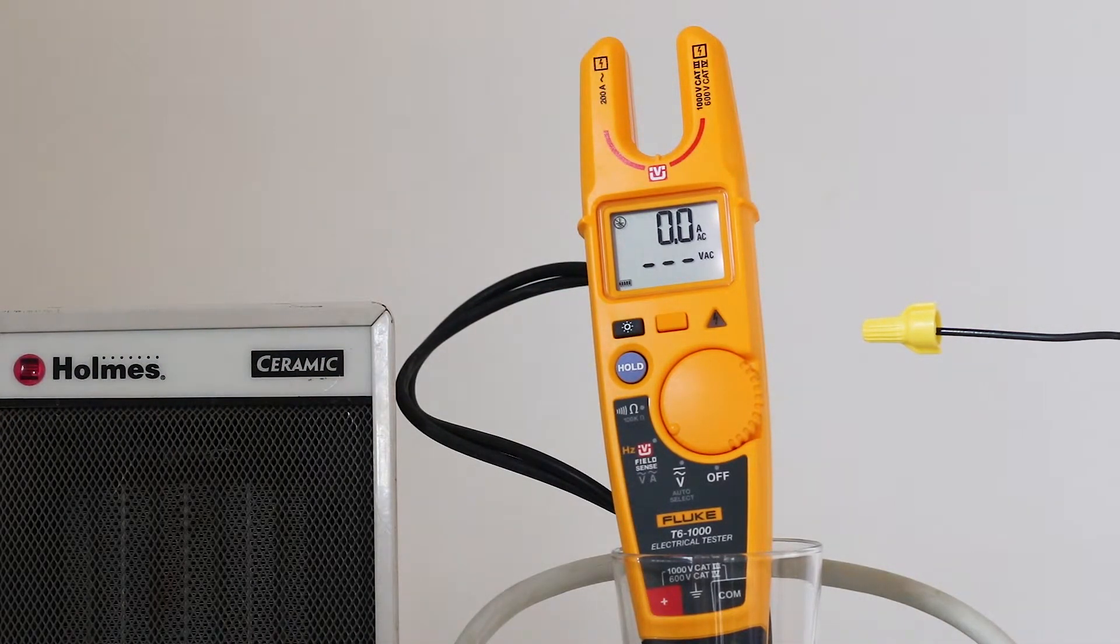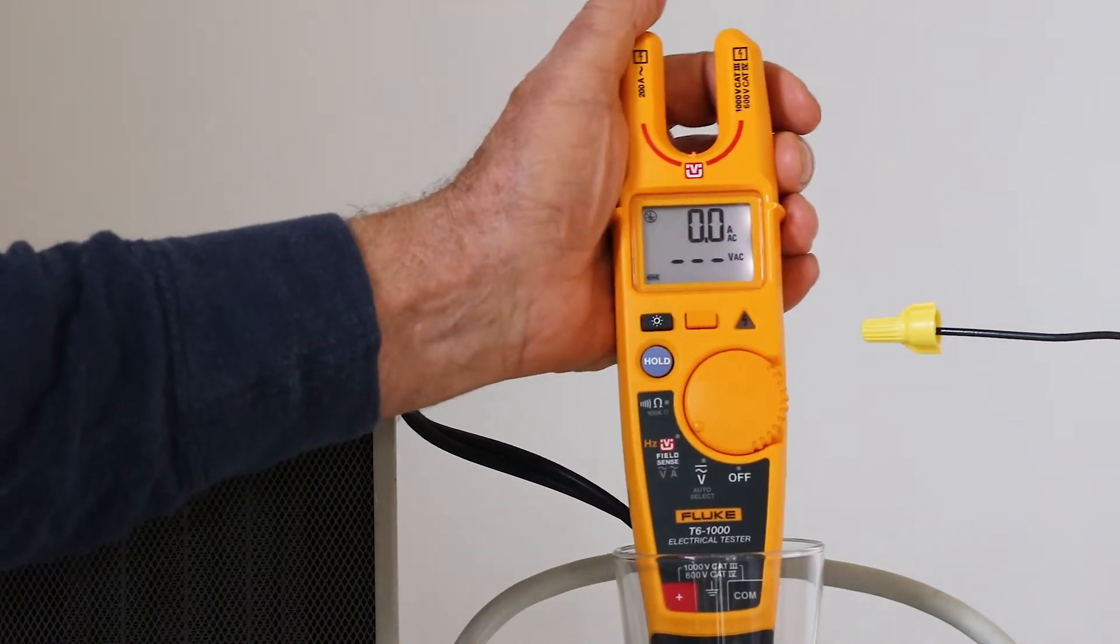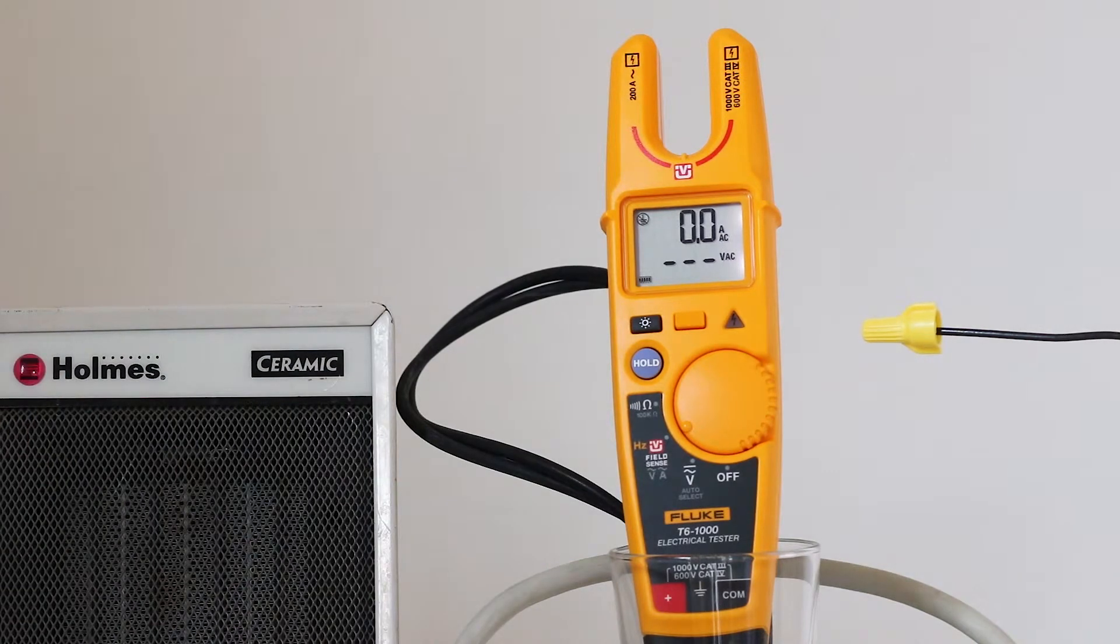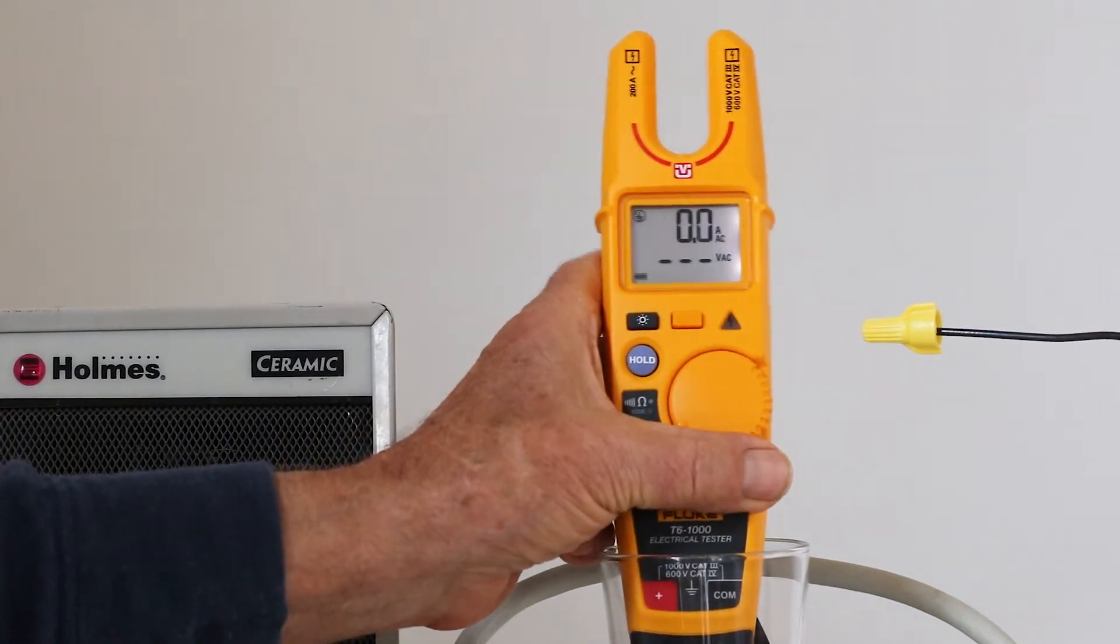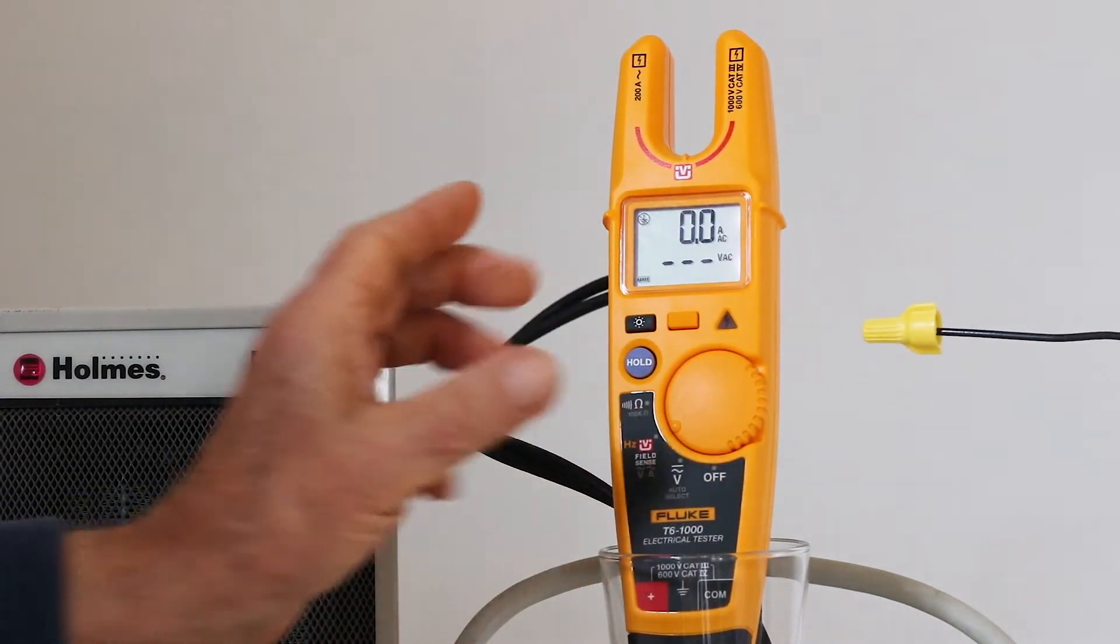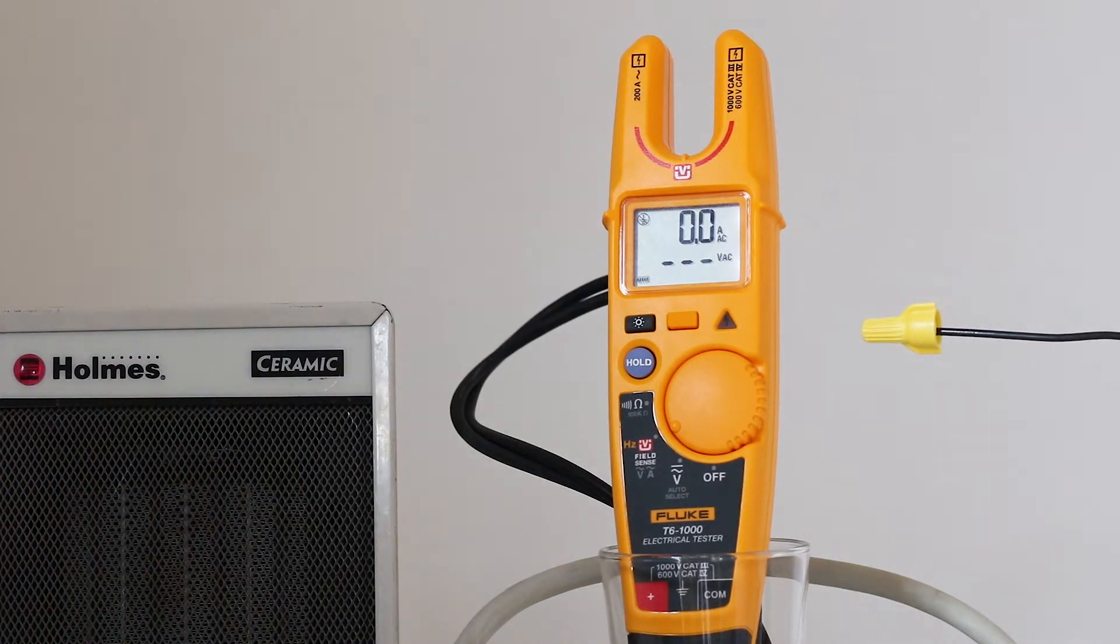The Fluke T6-1000 electrical tester resembles a clamp-on ammeter, but actually it operates quite differently. The clamp-on ammeter performs current readings by detecting a magnetic field surrounding a conductor through which the current is flowing. Of necessity, the jaws close around the conductor so that current can flow through the instrument's secondary coil. The T6-1000, in contrast, capacitively senses the electrical field surrounding an energized wire, even though there is no load and no current flowing.